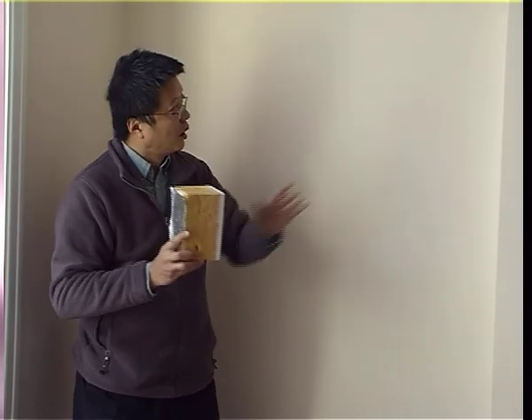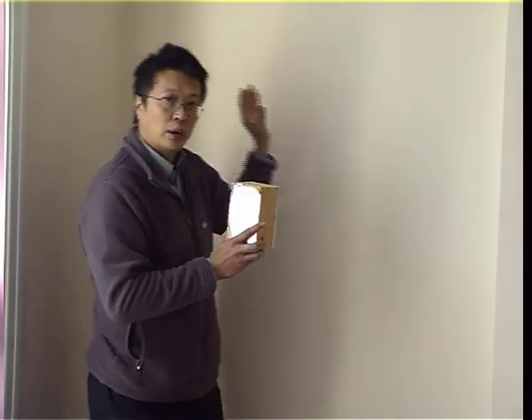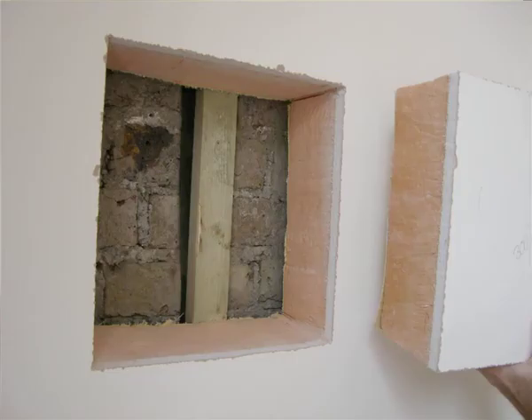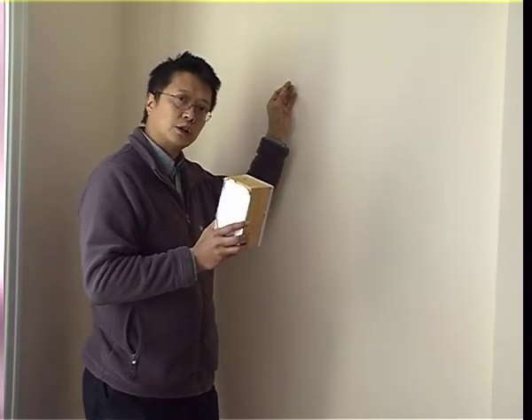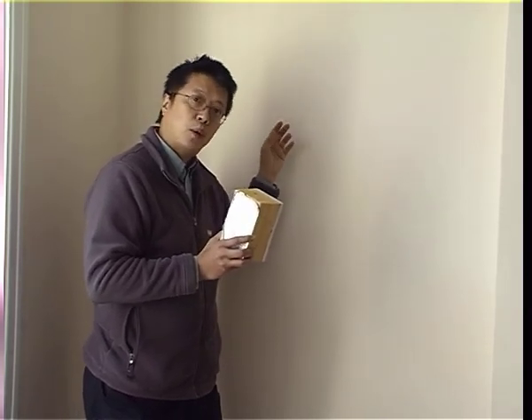One of the key measures we used in this house to achieve 80% carbon reduction was to insulate all the external walls on the inside using phenolic foam insulation, which was provided by our partners Kingspan. This has reduced the U-value on the walls by a factor of 10, from about 2 to 0.2.